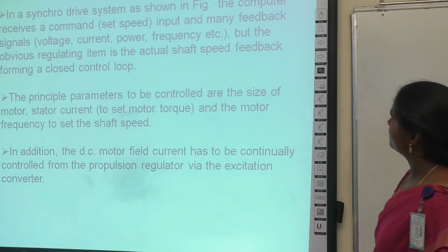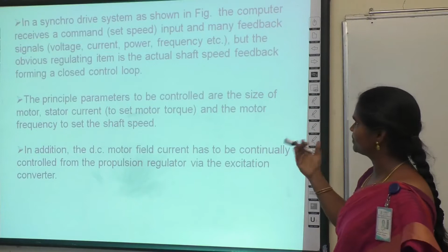In a synchro drive system, as shown in the figure, the computer receives a command input and many feedback signals like voltage, current, power, frequency. These are the feedback signals received. But the obvious regulating item is the actual shaft speed. Mainly, you are concentrating on the shaft speed. So based on the shaft speed only, the propeller will run the ship. The principal parameters to be controlled are the size of the motor stator current and motor frequency to set the shaft speed. These are the main factors for shaft speed. In addition, the DC motor field current has to be continuously controlled from the propulsion regulator via the excitation converter.